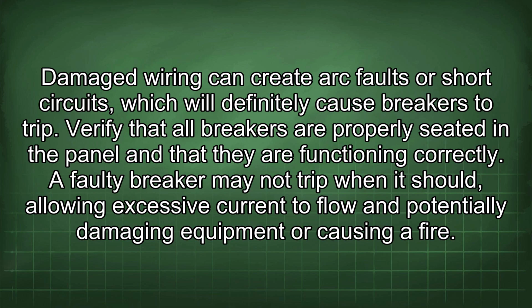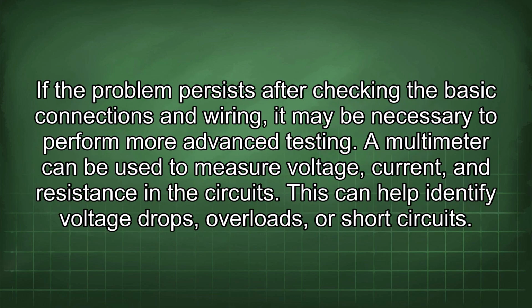Verify that all breakers are properly seated in the panel and that they are functioning correctly. A faulty breaker may not trip when it should, allowing excessive current to flow and potentially damaging equipment or causing a fire. If the problem persists after checking the basic connections and wiring, it may be necessary to perform more advanced testing. A multimeter can be used to measure voltage, current, and resistance in the circuits. This can help identify voltage drops, overloads, or short circuits.